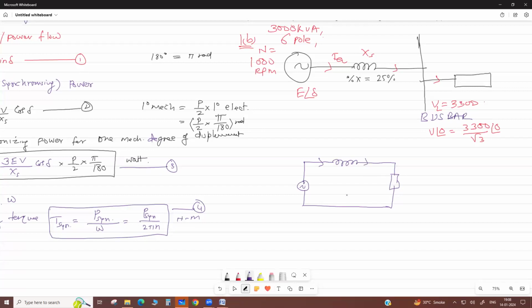So what is the full load current? Because it is a star connection, line current equals phase current, so it is per phase only. How do we calculate? KVA rating into 1000, divide by root 3 times VL; cos phi will not come here. So we calculate the current. What is the full load armature current?